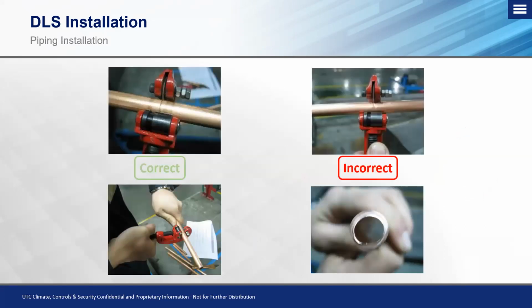So getting into the piping installation. When we're starting our installation, we need to make sure that we're cutting our copper pipe correctly. You can see on the left-hand side, you want to make sure that you have your cutting tool properly aligned and that it's not sitting at an angle, so that it doesn't cut the pipe and essentially put a bend in the pipe. You want to make sure it's a good, clean cut. Otherwise, our flare is not going to be correct when we go to do our flaring process. Okay, so you can see on the left-hand side, that's correct. On the right-hand side, you can see we're off center a little bit. So you definitely don't want to cut the pipe like that.